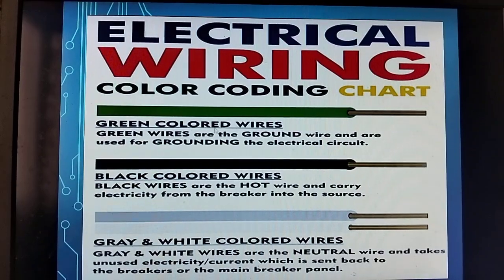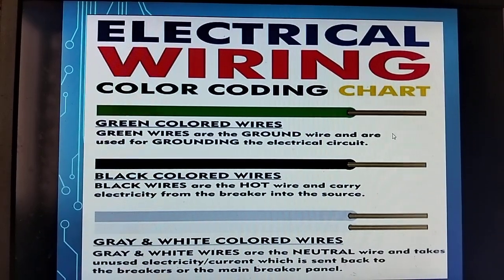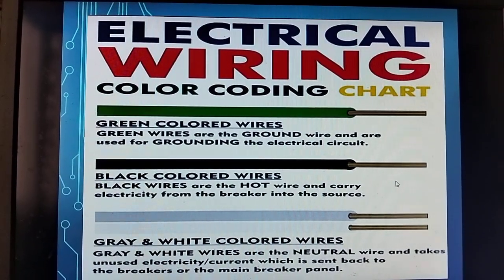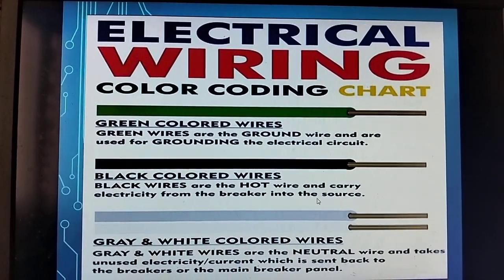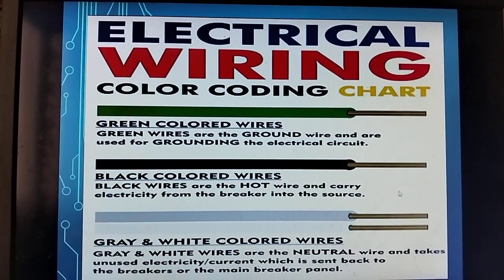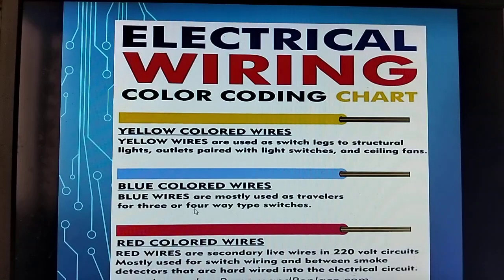The green is ground, or used for grounding the electrical circuit. Black color wires are hot wires and carry electricity from the breaker into the source. Gray and white colored wires are neutral wires and take unused electricity current, which is sent back to the breakers or the main breaker panel. The yellow colored wires are used as switch legs, to structural lighting outlets paired with light switch and ceiling fans. The blue colored wires are mostly used as travelers.